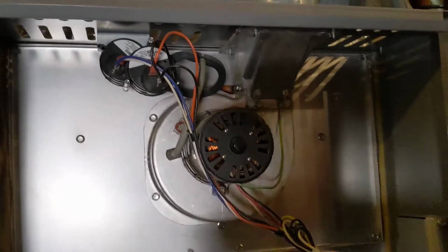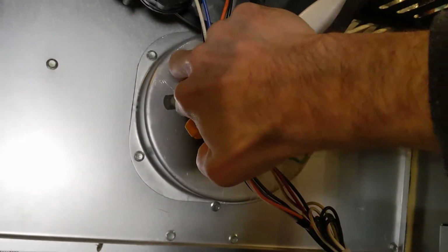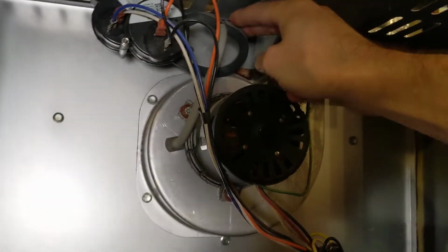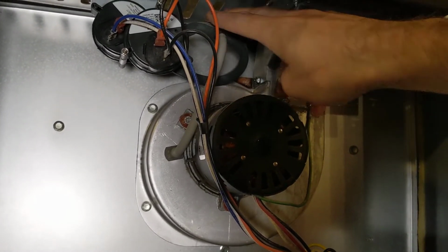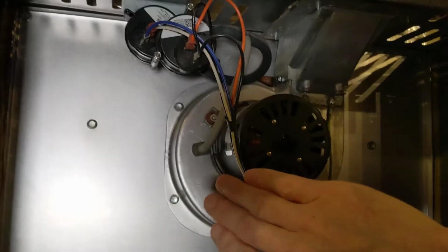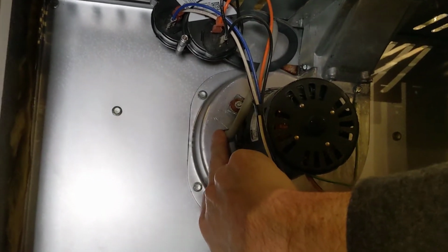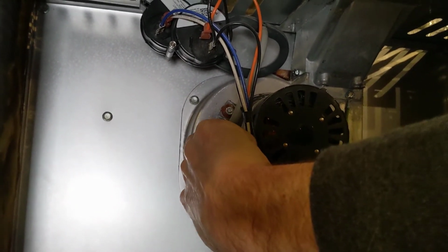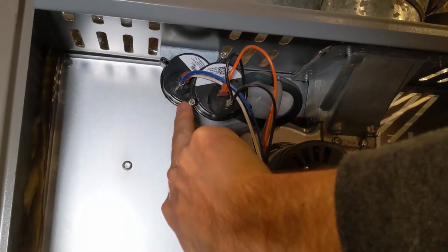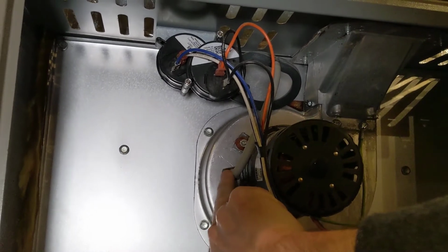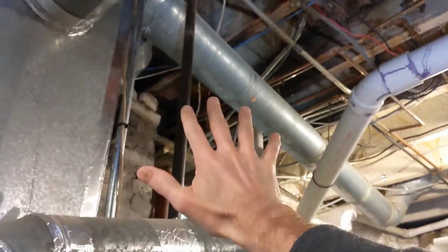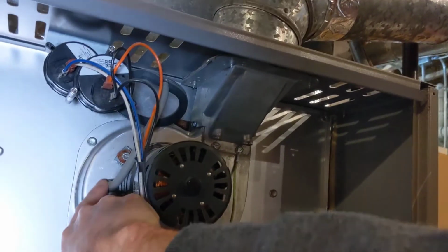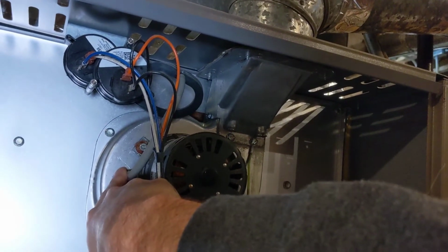One is that if you notice that this is physically using a rubber tube onto a port, sometimes you'll see two rubber tubes, like each switch is independent, but in this case it's one rubber tube split in between the two switches. The most common problem there is that this is clogged, because literally if this is clogged up, this can't provide the suction in order to physically close these switches. Very common problem is this inducer port gets clogged with debris, because remember this goes all the way to your chimney, and I've got a 100-year-old brick here, which means it's probably pretty dusty in there. That dust can collect and solidify inside this inducer port, and so I just need to clean it out.